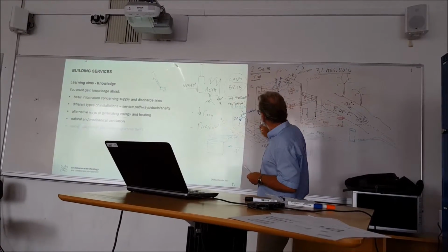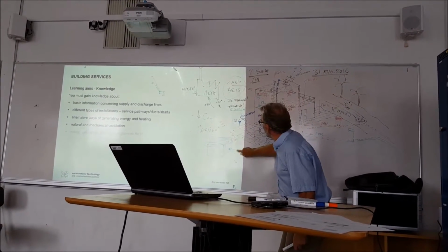So that would be your minus 20. And then what happens is you're getting the dirty air that's coming in at maybe plus 25 into this heat exchanger in the aggregate. That goes the opposite way in this heat exchanger. And the result coming out of that would be the combination of, if it wouldn't be minus 20, if you used the ground heating, it would be 0. Plus the 20, maybe you end up with plus 10 degrees, maybe plus 15 degrees.